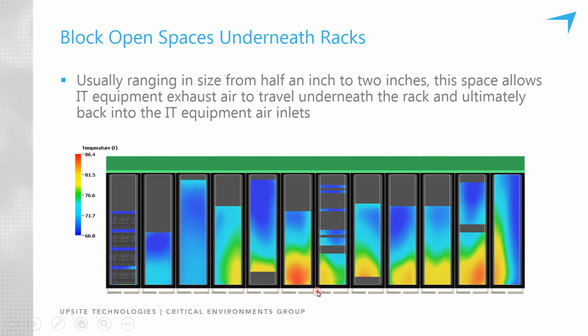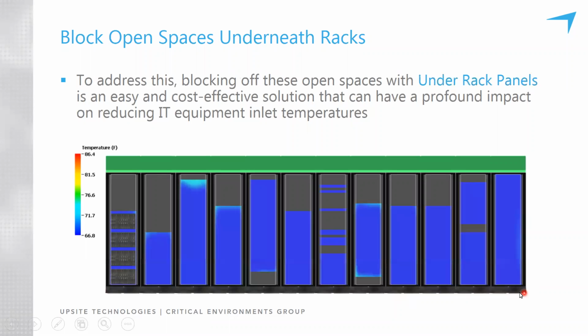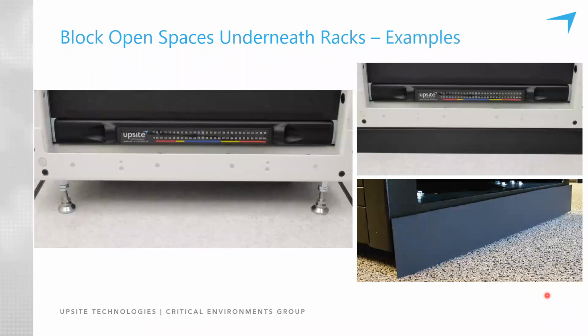So when these openings are sealed, you can see that the intake temperatures have dropped substantially. And these images are the result of detailed CFD analysis of a computer room. And there's a direct relationship between the evenness of intake temperatures and the efficiency of the room. The goal is always to get intake temperatures into all of the IT equipment, every single U, as even as possible. And that will directly relate to how efficient the room can become. So let's take a look at a couple of images of what these actually look like.